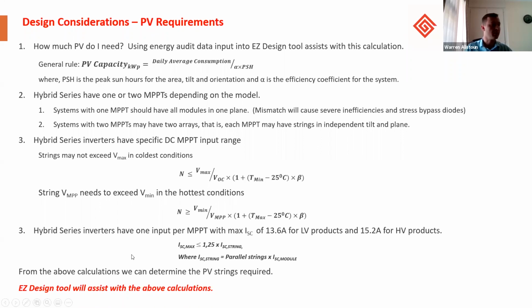Another aspect that we need to consider is the short circuit current of the panels to the inverters. For the low voltage products, we've got a maximum ISC of 13.6 amps. And for the newer high voltage products, 15.2 amps. The 15.2 amps allows for bifacial modules and the maximum yield from them. This is the equation here to determine the ISC max. Typically 25% above the ISC of the STC rating of the module, where the ISC of the string is the parallel strings times the ISC of the module. Using standard poly or monocrystalline panels, you'll typically just have one string going into the inverter. When using thin film, the parallel strings will come into effect.